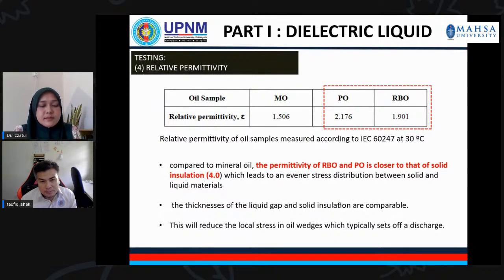So the second dielectric property is related to the relative permittivity, and relative permittivity is one of the important factors which show how the oil behaves in the electric field. In simpler words, relative permittivity indicates how easily a material becomes polarized under the electric field. Based on this study, we measured the relative permittivity of the oil samples according to IEC 60247 at 30 degrees C. For palm oil it is around 2.176, and for rice bran oil it is 1.901.